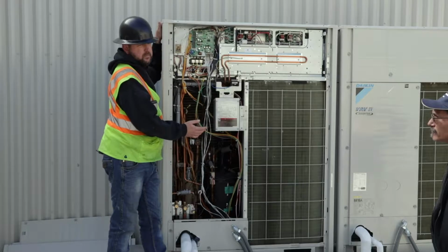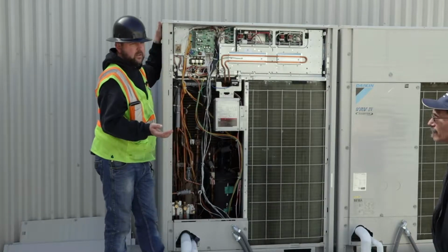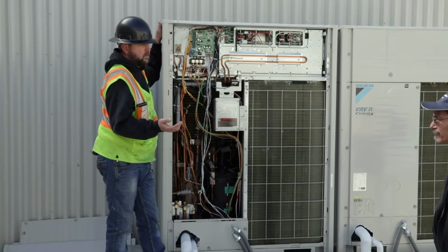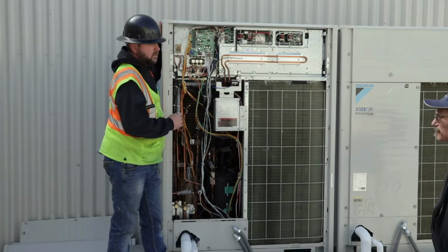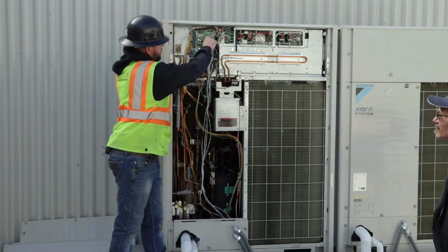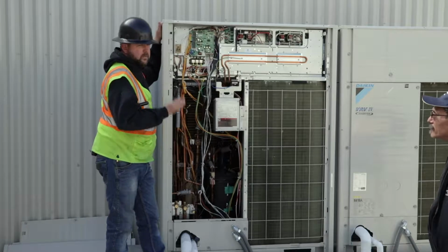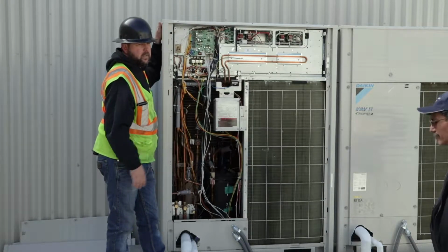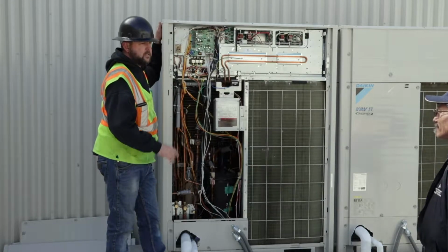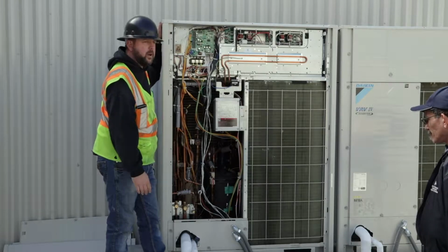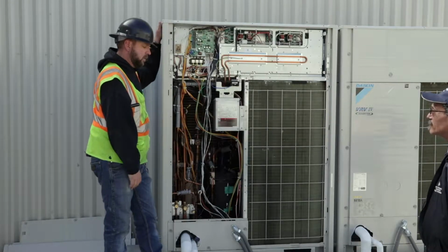They are heat pumps, but being that they only serve your TR rooms and your electrical rooms, we made them cooling only units. We did that with this dip switch right there. Flip that up, and it makes them cooling only, so no one can go to the thermostats and try to put them in heat. It won't happen. It locked out the heat mode.